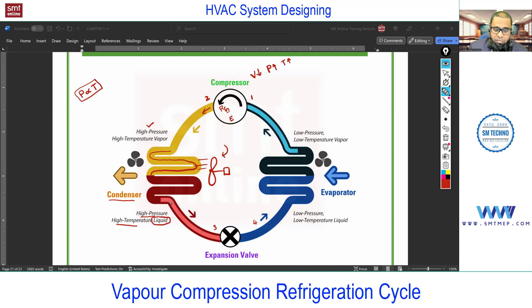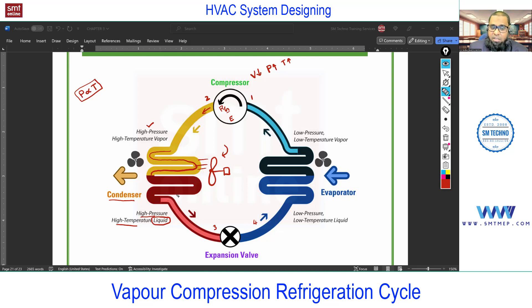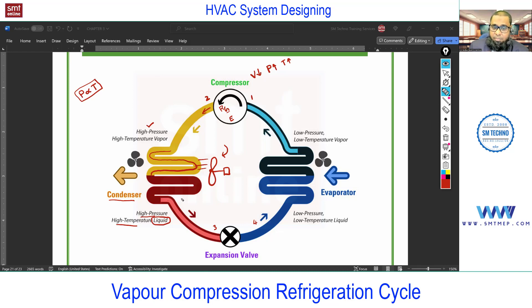You know that a change of phase means latent heat at constant temperature, so temperature remains the same but the phase changes in the condenser. The fan must be designed accurately — not to lower the temperature but for heat rejection. Based on that, the manufacturer designs the flow rate, number of coils, thickness, and diameter of the coil. The manufacturer designs the condenser to reject heat equal to the latent heat; then only the change of phase is possible. So temperature and pressure remain the same but phase changes.